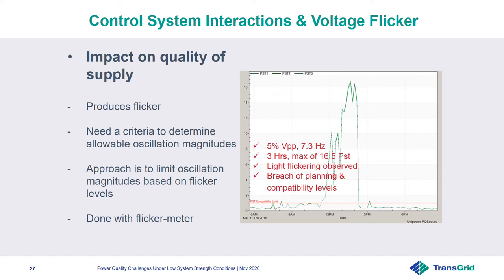So we looked at the impact of these small oscillations. These oscillations produce flicker. This is an example of recorded flicker levels from an event that caused 5% voltage peak to peak oscillation at 7.3 Hz modulation frequency.